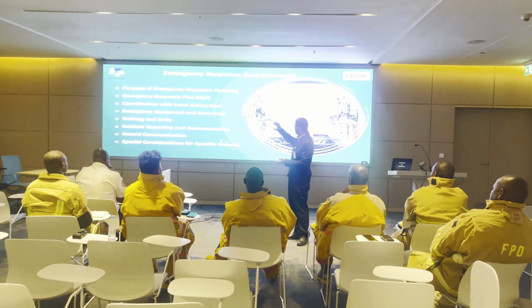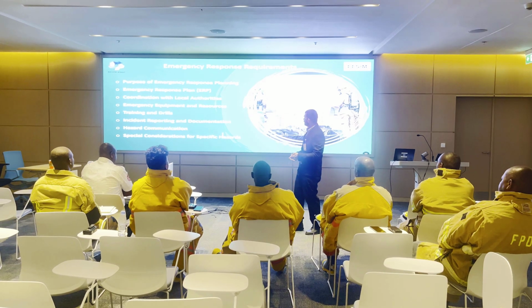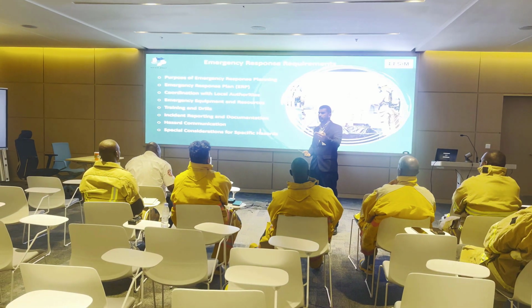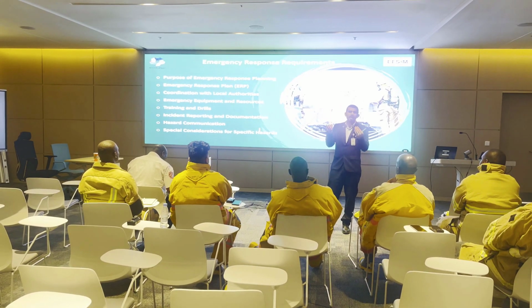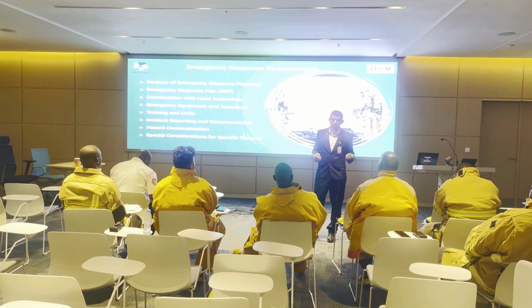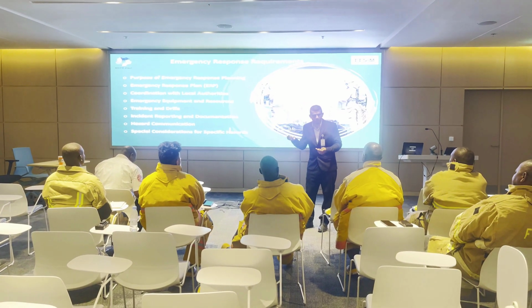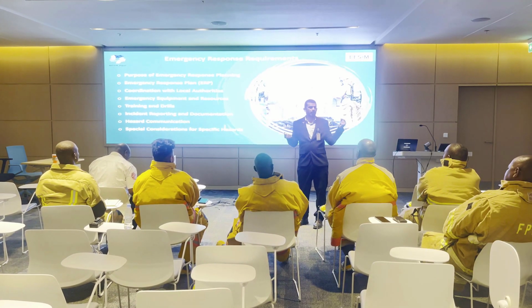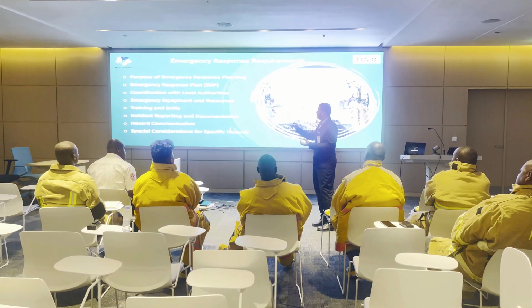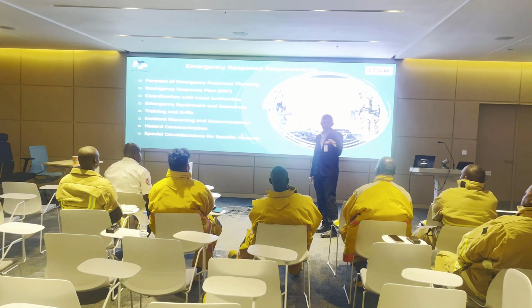Emergency response planning is most important before any incident or accident happens. There should be an emergency response plan for every place and every hazardous material. Like we have a medical gas storage area, so we should have an emergency response plan. If there is a fire in the medical gas, what is our strategy? If the medical gas leaks, what is our strategy? Where can we shift the persons, where can we gather all the staff, where is the wall, who is responsible for the call to 911, who is responsible for 444, who can coordinate with the Ministry of Health? Everyone should know their duties and they should be written in the emergency plan. So an emergency plan should be made for every site or every place of work.